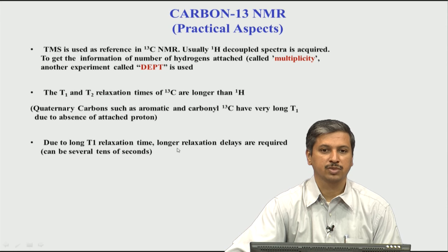So, in that picture the time delay between when the FID is collected and the next pulse we call the relaxation delay, and that relaxation delay, if you remember, we said depends on the T1 value. So, typically the relaxation delay is about 4 to 5 times the T1 value of the sample. So, for protons it is typically a second. That means, if I want a long relaxation delay, 1 to 2 seconds is a typical T1 of protons for small molecules. So, for proton NMR we typically use a relaxation delay of 5 to 10 seconds, typically it is not more than 5 practically.